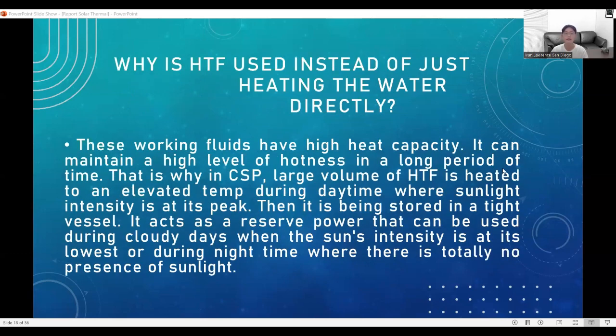So, why is HTF used instead of just heating the water directly? These working fluids have high heat capacity. They can maintain a high level of hotness for a long period of time. So, that is why in CSP, a large volume of HTF is heated to an elevated temperature during daytime, where sunlight intensity is at its peak. Then it is stored in a tight vessel. It acts as a reserve power that can be used during cloudy days when the sun's intensity is at its lowest, or during nighttime, where there is total absence of sunlight.